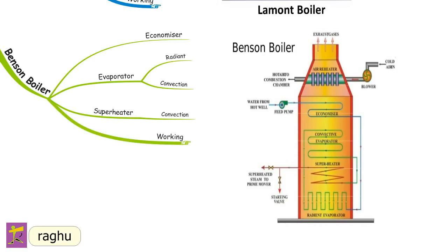In the working of the Benson boiler, complete heating, steam generation, and superheating are done in a single tube. Feed water flows through the economizer tubes and then through the radiant parallel tube section to evaporate partly. The remaining water in the radiant evaporator is evaporated into steam in the convection evaporator by hot gases. The saturated steam from the evaporator passes through the convection superheater where it is superheated, and finally the superheated steam is supplied to the steam turbine. The capacity of the Benson boiler is about 750 tons per hour.